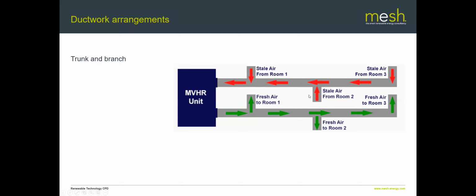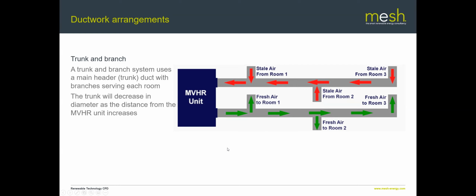This is the first common arrangement, what's called a trunk and branch system. In a trunk and branch system, you have a main trunk duct, and from that, little branches go off and serve each room. This is typically the arrangement you use when you've got a fair bit of space in your ceiling voids, or if the building is quite long and thin, it can be quite a good option because it suits the geometry of a trunk and branch system. It can be slightly more problematic in a much squarer building, or one where the ceiling void isn't so generous, and physically finding the space for this big trunk duct might be challenging. So that's what a trunk and branch system is.